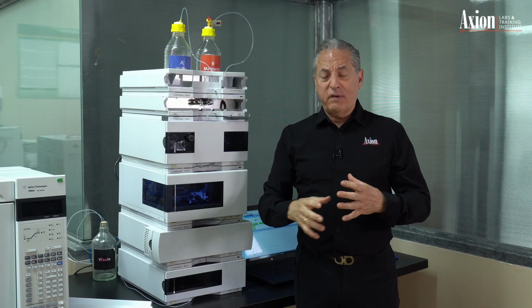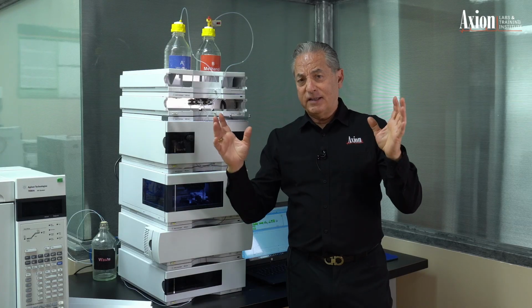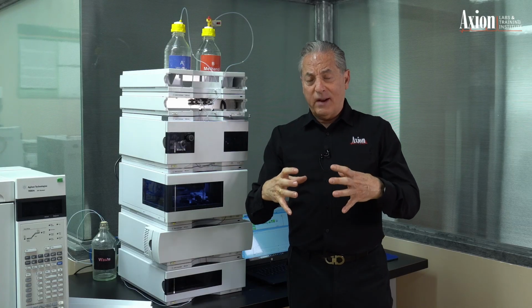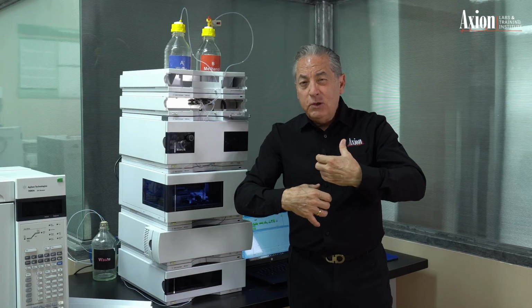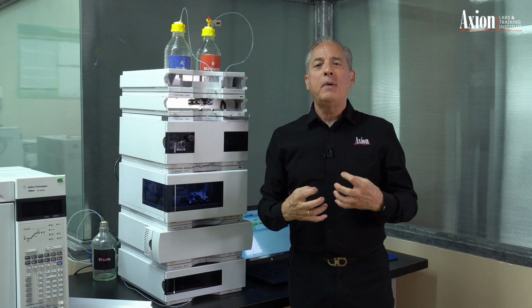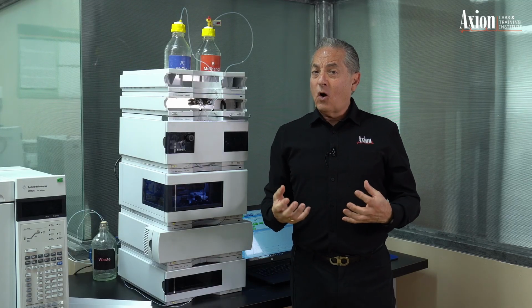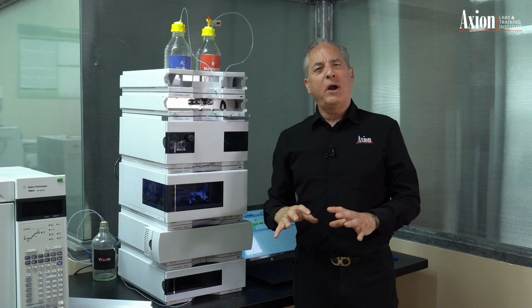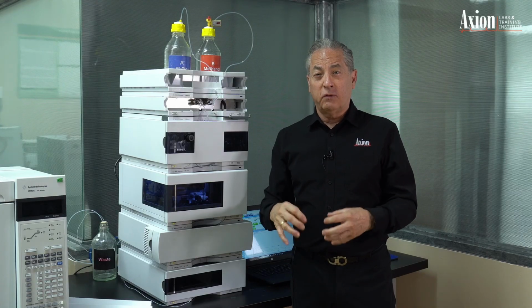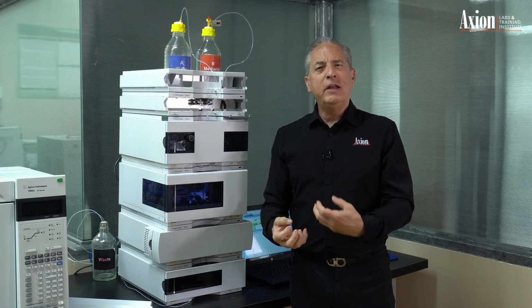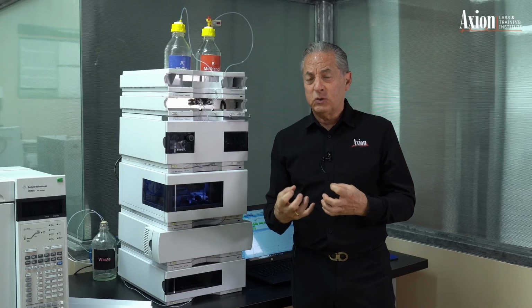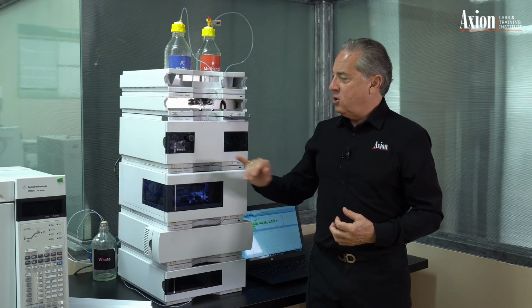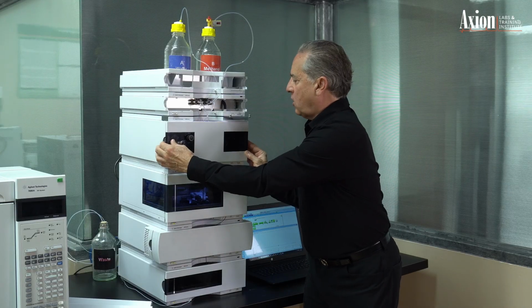You probably know if you have a brand new bottle of, let's say 7-Up or some kind of a soda, when the bottle is closed, there's no bubbles. But as soon as you crack the top, as soon as you open it up, you see bubbles appear. Those are carbon dioxide bubbles that under pressure, carbon dioxide was in solution, dissolved in the liquid. And as soon as you lower the pressure, those bubbles come out of solution. So if that happens in your HPLC pump, that's going to cause problems.